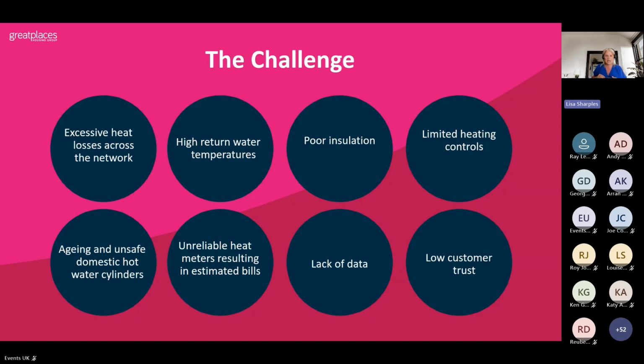The challenge here is really clear. The local housing team were struggling with excessive heat losses across the network, high return temperatures, and flow and return temperatures practically the same, with no delta T. There was poor insulation, common on legacy heat networks, and customers had limited control, as did the plant rooms. We had aging equipment and unsafe domestic hot water cylinders within the property.